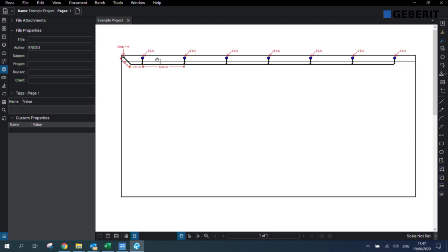As you can see, we've got a simple project example set up over here where we have seven outlets with each outlet receiving a flow rate of nine liters per second. We're dropping here seven meters on the left before our discharge point. This will be the project that we're going to size today.